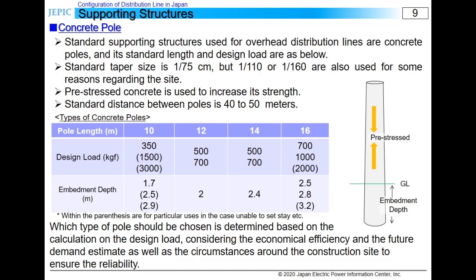The standard distance between poles is about 40 meters or 50 meters, and which type of pole should be used is decided considering the future demand, cost, site situation, etc. Then, by doing appropriate calculation, the supply reliability is kept.